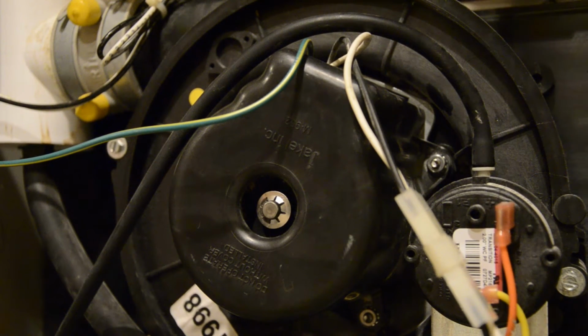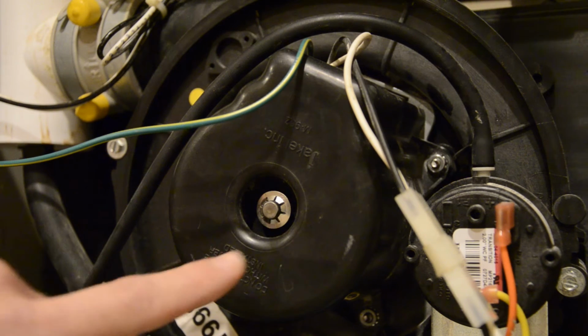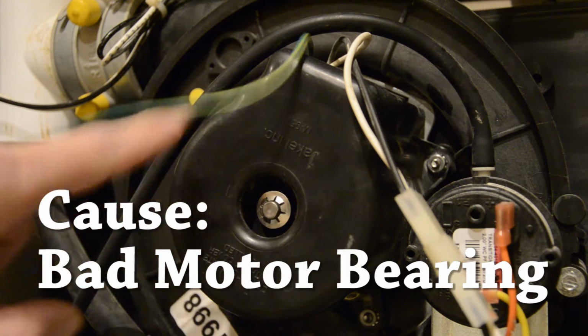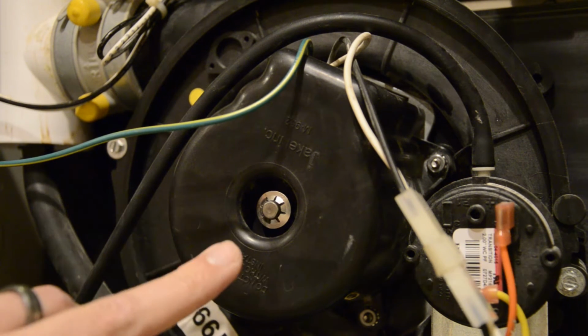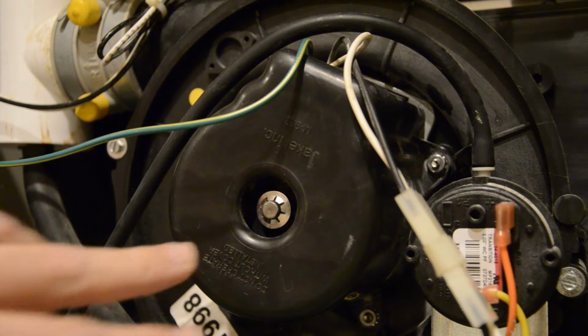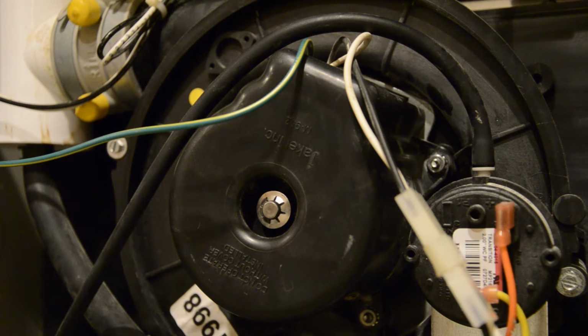This did not fix the problem for me. My issue was the exhaust motor. The cause is a bad bearing. When the furnace turns on, the motor tries to spin, but with the bearing being stuck, it would not turn on. You can hear the hum of the motor, but no spinning.